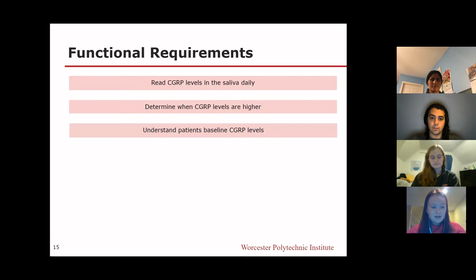In order for the device to be determined as successful, it must maintain basic functional requirements when implanted into the body. The functional requirements of our device include that the device must read the CGRP levels in the saliva of the patient on a daily basis. The device must be able to determine when the CGRP levels are higher than normal. The device must be able to understand the patient's baseline levels of CGRP. The device must be able to alert the patient of an oncoming migraine. The sutures of the device must maintain the device's placement and negate any migration. And lastly, the wash buffer with the device must clear the CGRP molecules from the antibodies.